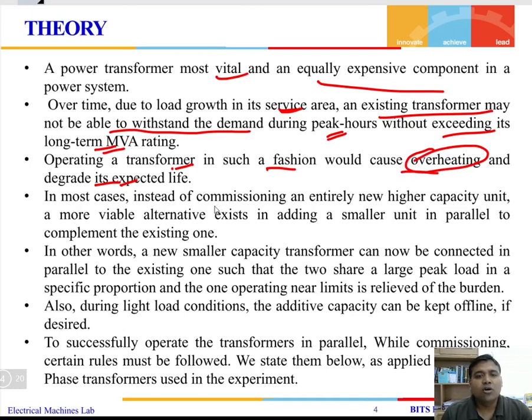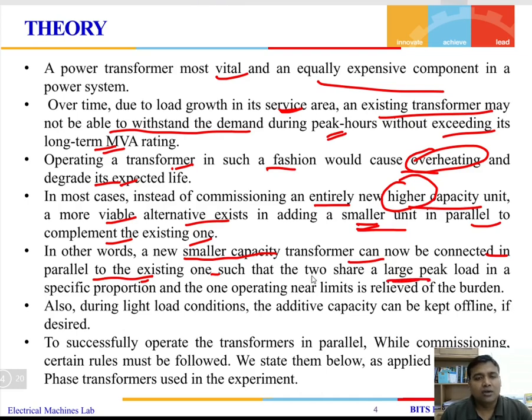In such cases, instead of commissioning an entirely new higher capacity unit, a more viable alternative exists: a smaller unit in parallel to complement the existing one. So instead of bringing in a new transformer of higher capacity, we take a smaller transformer and put it in parallel with the existing unit. In other words, a new smaller capacity transformer can be connected in parallel to the existing one to meet the large peak load that generally arises, and which increases the burden on the transformer. During the light load condition, the additional capacity can be kept offline. So whenever the load demand decreases, the transformer that was brought in parallel will be switched off so that it is not being used.